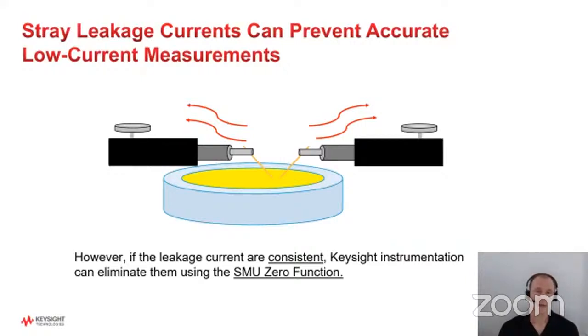Now, especially if you're making measurements on a wafer, although this also holds true for packaged devices but is more prominent on wafers, you'll find that the probes and some of the other cables will have stray leakage currents associated with them that make it very hard to make a low-level current measurement. But fortunately, if those currents are consistent, we have a way to subtract them out automatically so that you can reduce them and get more consistent and better measurements.